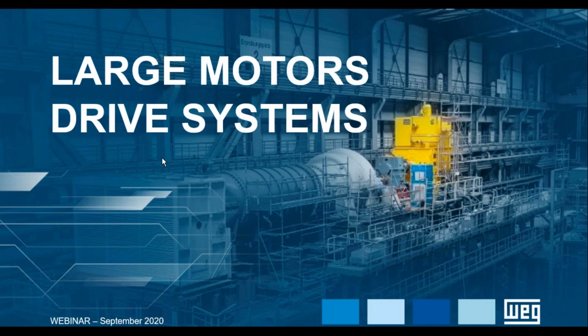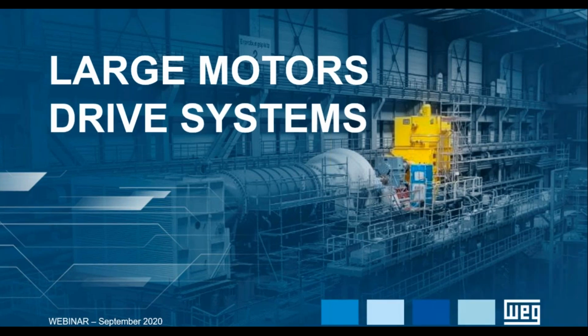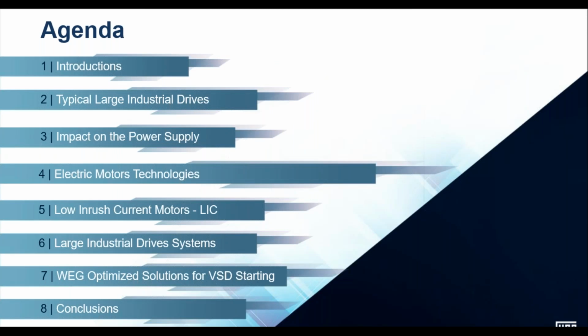The presentation title is Large Motor Drive Systems. Just to define a large motor drive system, when I'm talking drive in the context of the title, it doesn't necessarily mean a variable speed drive. It actually means it can be applied with any other indirect starting device, or it could just be a motor on its own. But really, we're going to take a holistic view of the different motor types and the different starting types, hence the term drive systems. Just to define a large motor drive system, in fact, we're talking about large motor industrial drive systems. So to define that, we would be talking large megawatt ranges, let's say for the purpose of this discussion, more than 1 megawatt, and definitely more than 1000 volts, typically 3.3 kV and above.